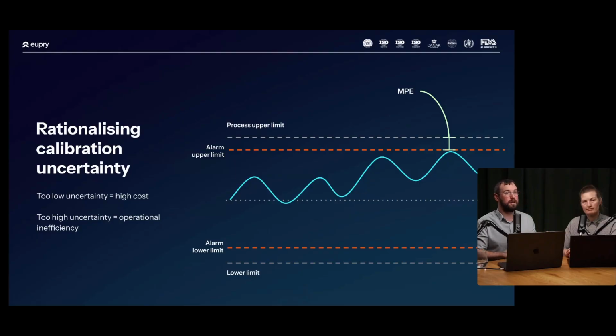As you can see from the depiction here, whenever we set a process limit, let's say it's 25.00 degrees, we need to subtract the MPE, which would be 24.5 degrees Celsius, because if we had a measurement of 25 degrees, that would actually, with our MPE, be outside our operational range. And again, on the other side, choosing too high of an uncertainty can have operational inefficiencies. You're going to have a lot of alarms if you choose an uncertainty that's very, very high.